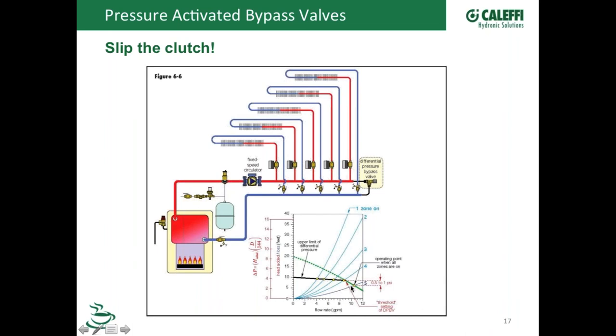give us, let's go out here, what do we got? With all the zones open, maybe we've got 11 GPM going through that. So on a design day, we need to move 11 gallons a minute through this entire system. Maybe we've got a 110,000 BTU boiler. So we're going to size that circulator to handle this job under design condition when all the valves are open.